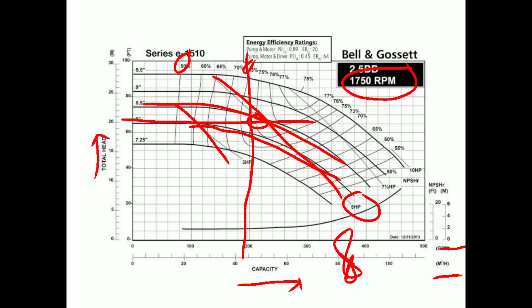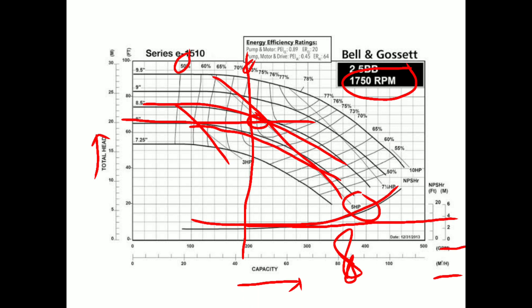We will also see the net positive suction head (NPSH) requirement. Our vertical line from 40 cubic meters per hour intersects the NPSH curve. Drawing a horizontal line from that intersection point, we see it is about 3 meters. So we need a 3 meter suction head to avoid cavitation in the pump. This is how we calculate different parameters from the given flow and head requirements.